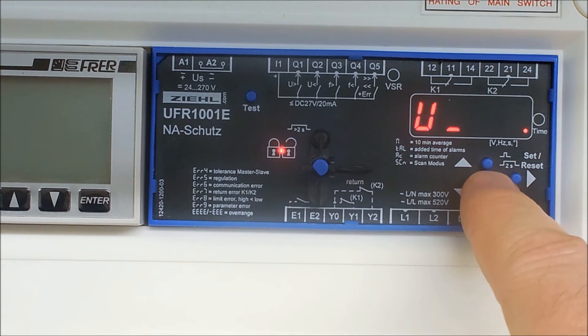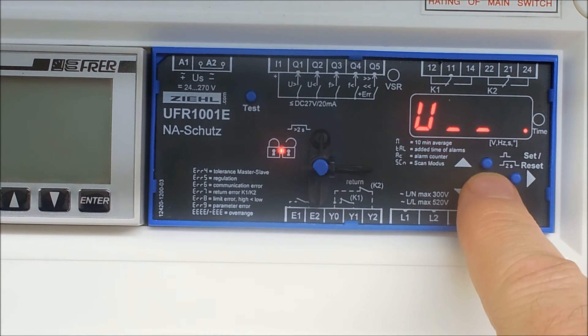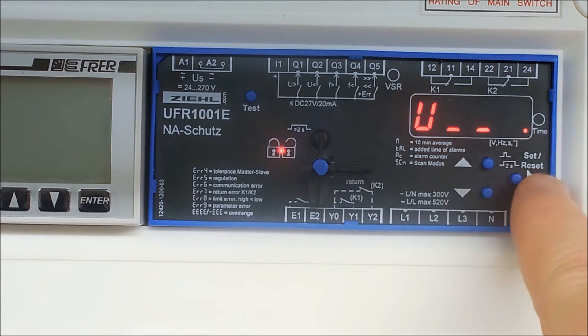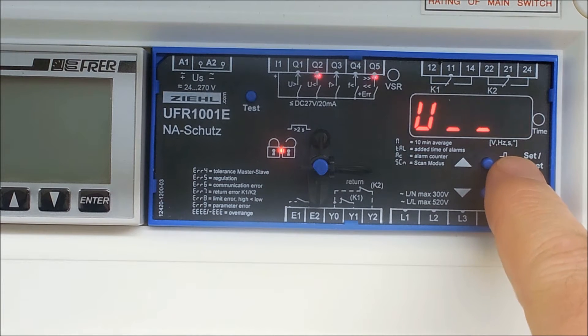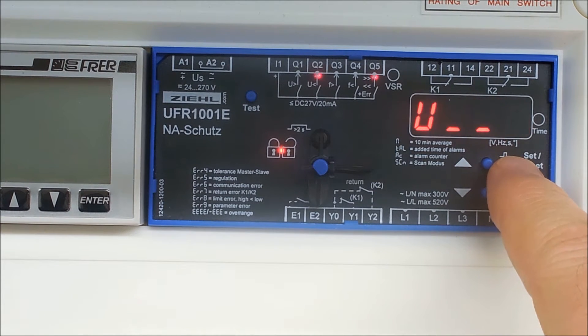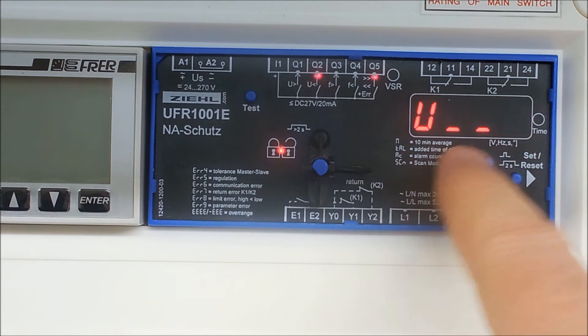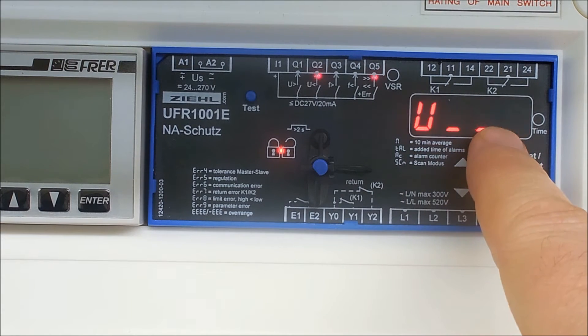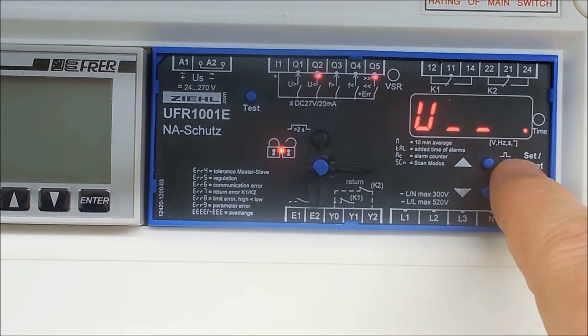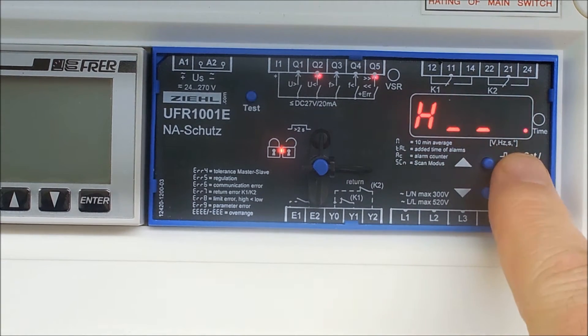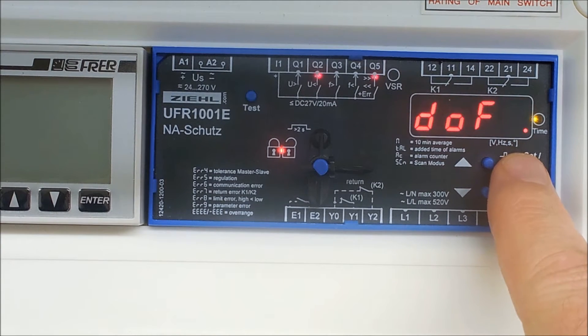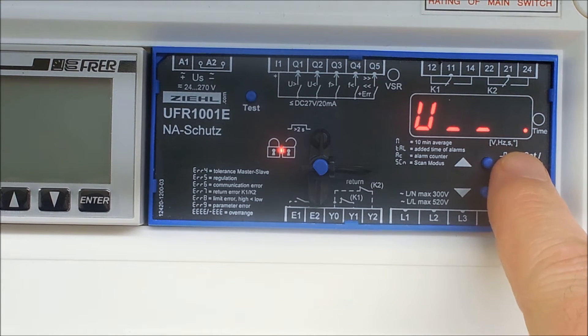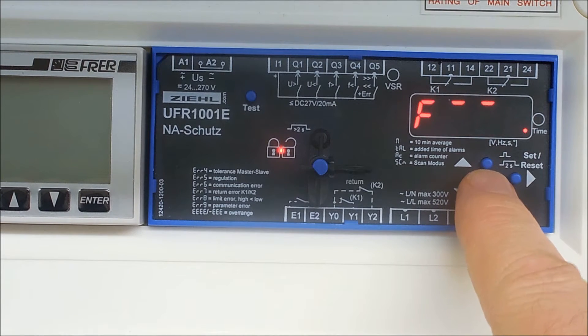You also then have under voltage the first level, under voltage the second level and all of the values always have of course the on value indicating that unit is being monitored. If you don't want that value to be monitored you can change that to off during the program mode. You then have the value itself, you then have the hysteresis, the delay and then you have the delay off for the reset and then back to the main menu again.